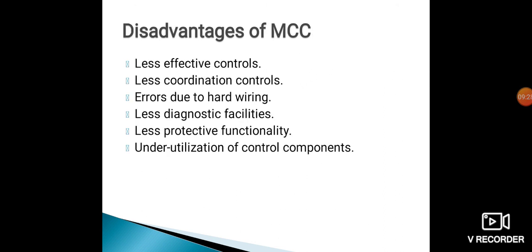The disadvantages of MCC include less effective controls, less coordinated controls, and errors due to hard wiring — since wires are tightly coupled with each other, there is a chance of errors occurring. There are also less diagnostic facilities, less protective functionality, and under-utilization of control components, as not all installed control components are necessarily used every time. This was all about the introductory part and the role of the MCC. If you have any doubt, you can contact me. Thank you.